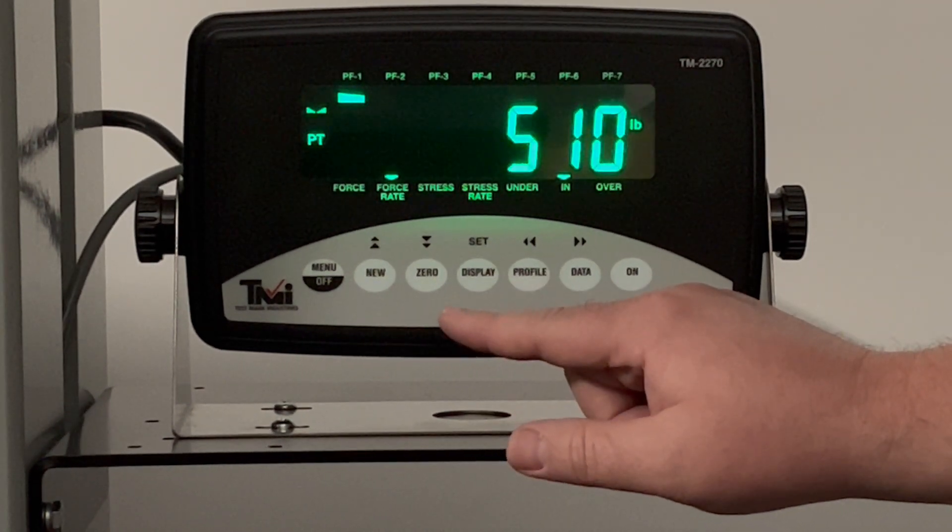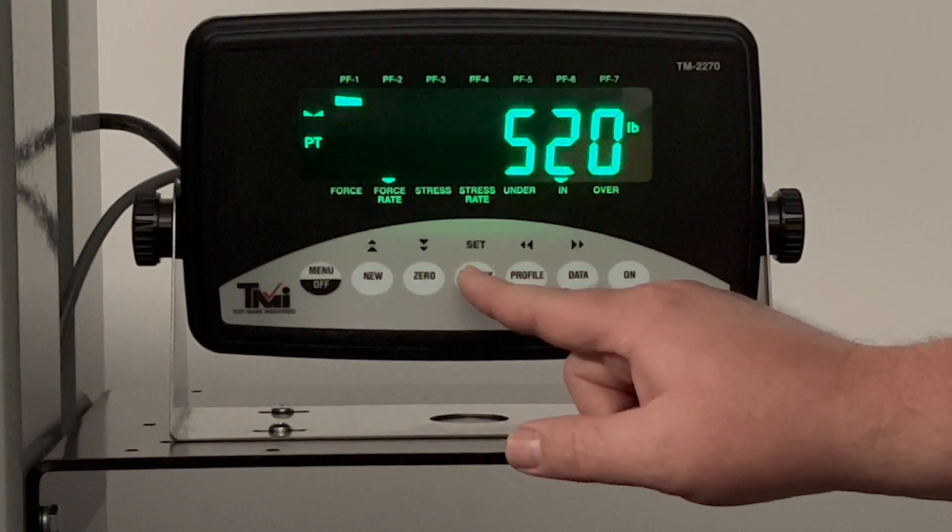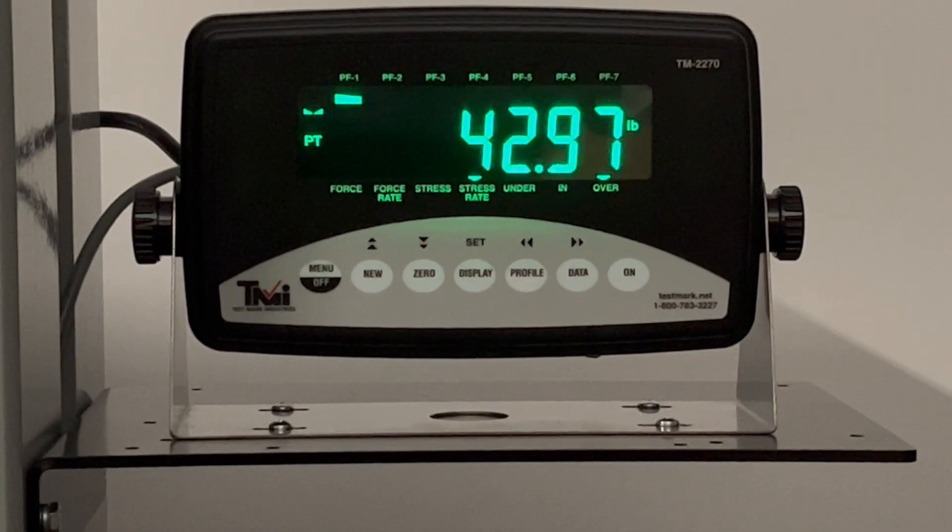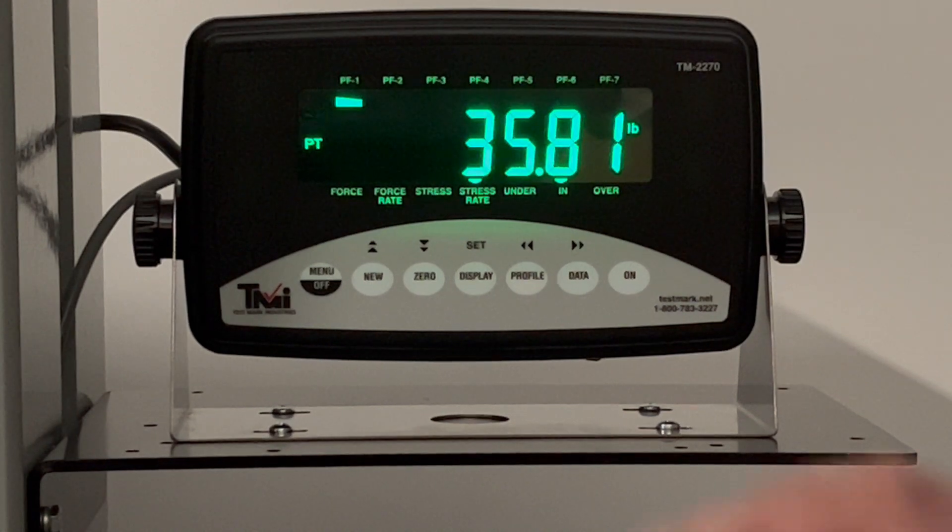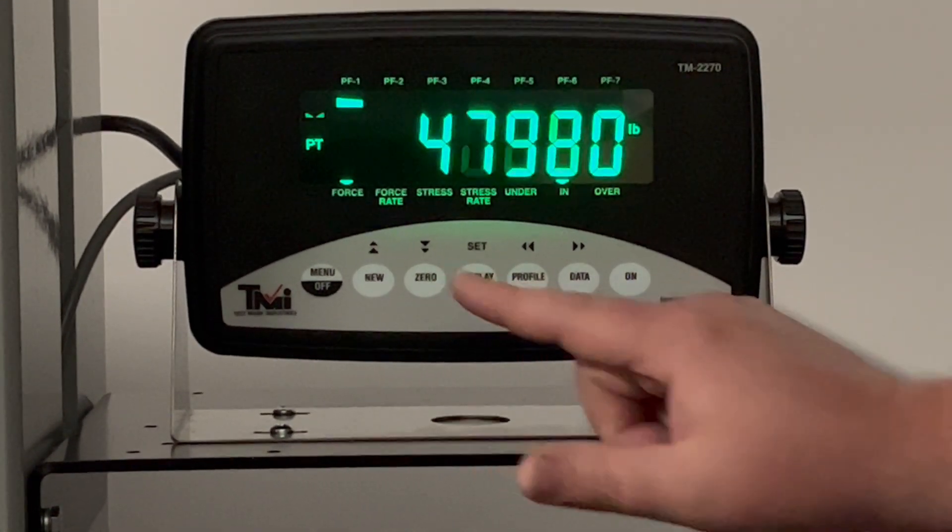Push the display key again, and it will go to force rate, which is in pounds per second, and stress rate, which is in psi per second. And again, back to pounds.